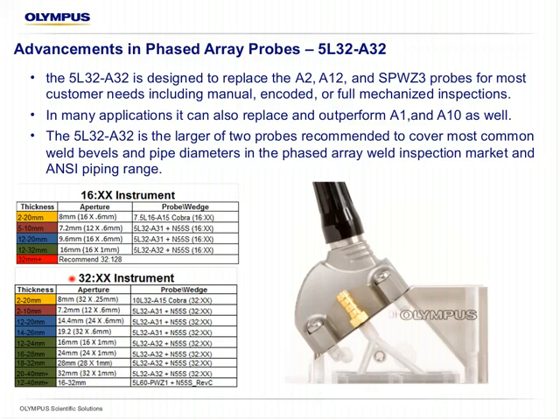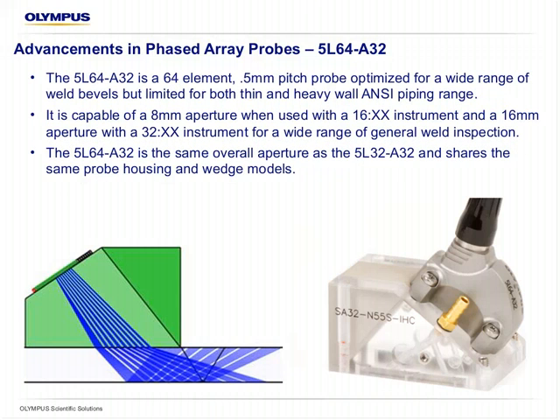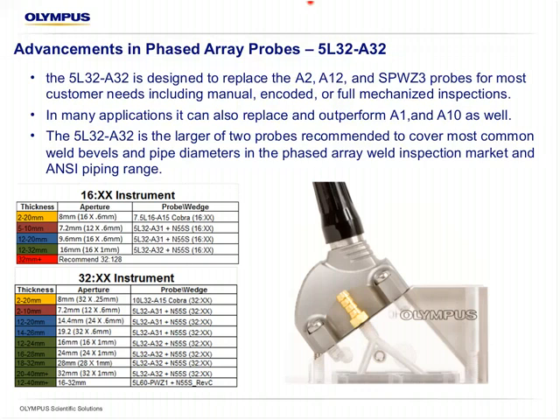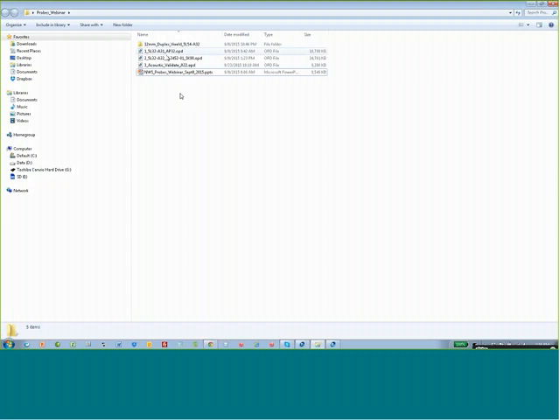The two probe combination of the A31 and large pitch A32 would give us a very large range of the ANSI piping chart and perform most inspections, even heavy wall thick vessels. And again, we have two versions of this A32 that we will demonstrate the difference shortly. So another data example using the heavy wall 5L32A32 is a 25 millimeter double V weld.